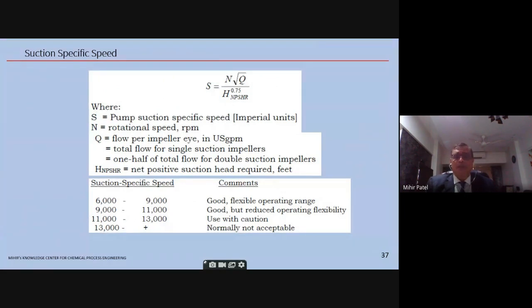Now, there's a certain upper limit which needs to be maintained. In the 1980s, a lot of refineries used to keep very high suction specific speeds. So that used to give a very low NPSHR. What this basically means is that the suction vessel height comes down, so you are saving in the capex of the structures, etc. But then the pump started giving a lot of problems. Investigation was done, and this upper criterion was established. So now UOP, for example, keeps a higher limit of 11,000. They don't go above 11,000.